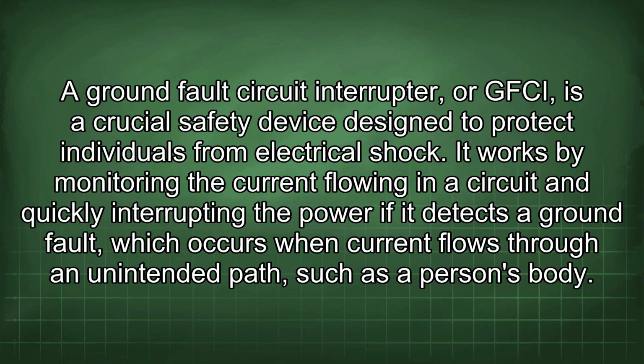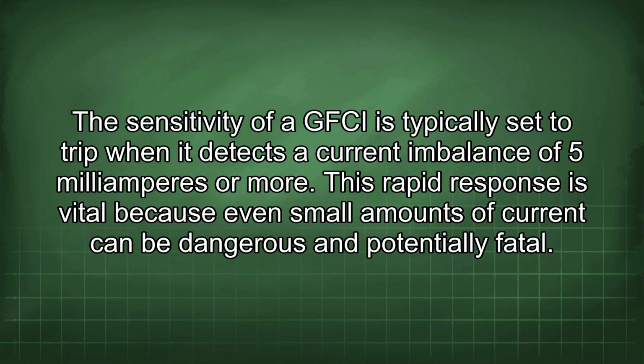A ground fault circuit interrupter, or GFCI, is a crucial safety device designed to protect individuals from electrical shock. It works by monitoring the current flowing in a circuit and quickly interrupting the power if it detects a ground fault, which occurs when current flows through an unintended path, such as a person's body. The sensitivity of a GFCI is typically set to trip when it detects a current imbalance of 5 mA or more. This rapid response is vital because even small amounts of current can be dangerous and potentially fatal.